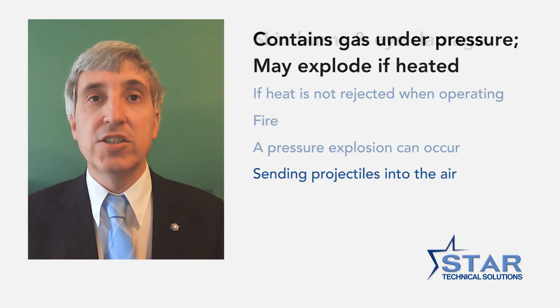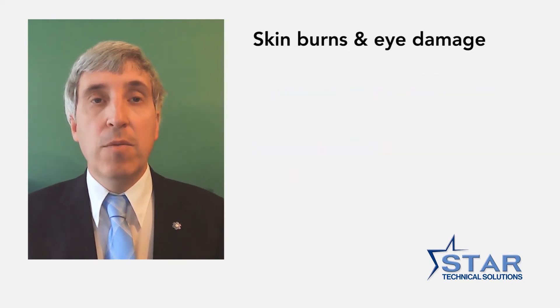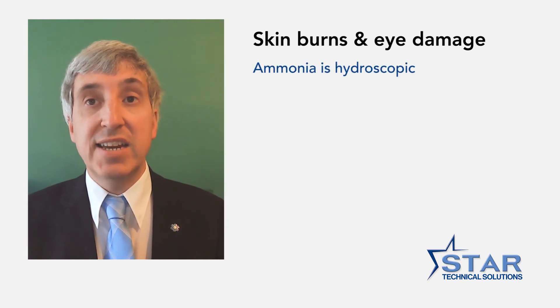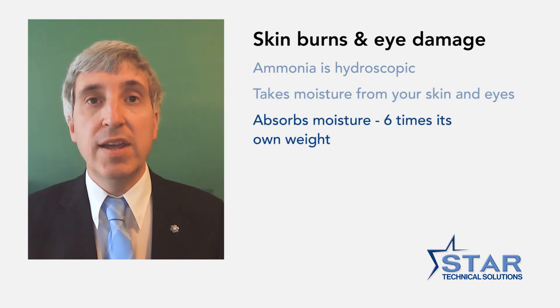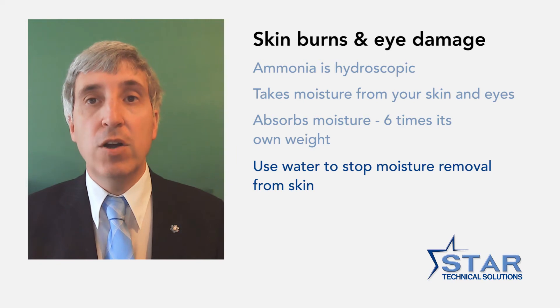The fourth hazard associated with ammonia is skin burns and eye damage. Ammonia is hygroscopic and therefore if ammonia is released, it seeks out moisture. When ammonia liquid is in contact with human tissue like skin and eyes, it draws the moisture from the human tissue as it consumes six times its own weight in moisture. The only treatment is water — lots of water and then more water. Flushing the burn with water gives the ammonia an easier source of moisture to seek out, pulling it away from the human tissue.